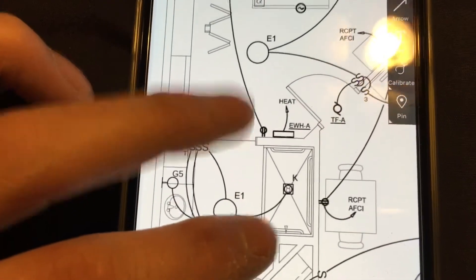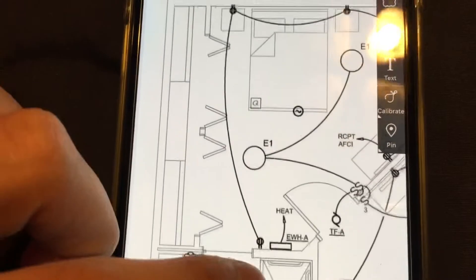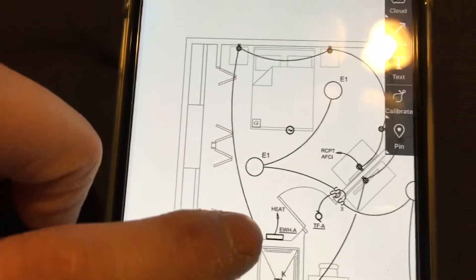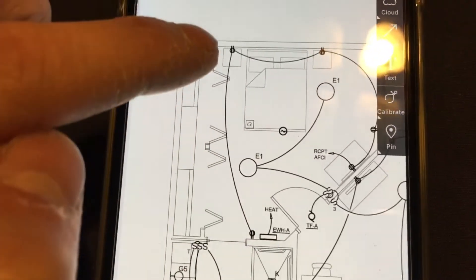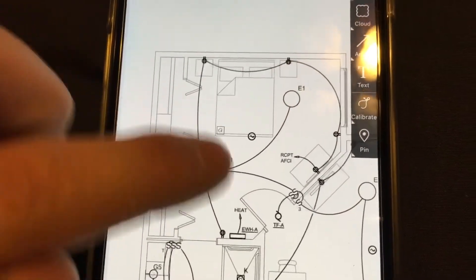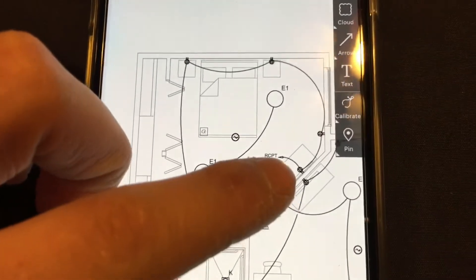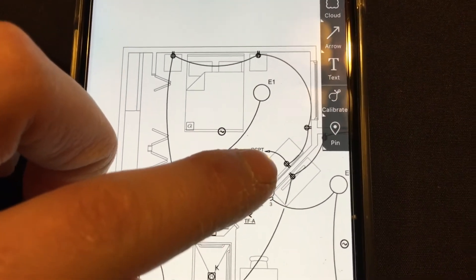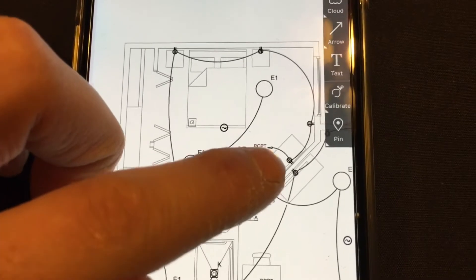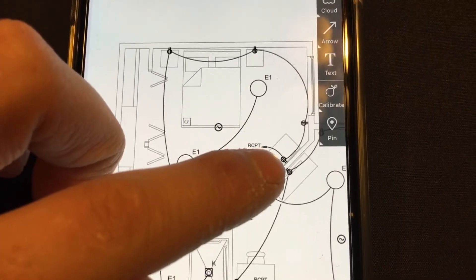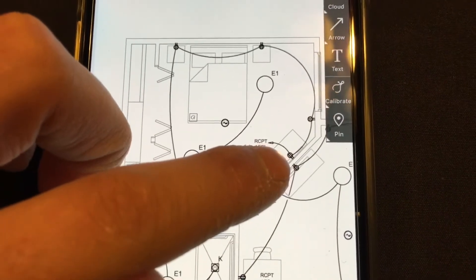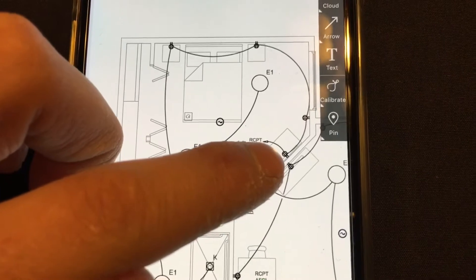So this is the plug symbol. There's plugs here, and then the lines represent the circuits. So this is a circuit right here. This little arrow represents a home run back to the panel, so that's the power source. It starts here in the first plug, it jumps from there. So you got the one home run wire and then the second wire goes to this plug.